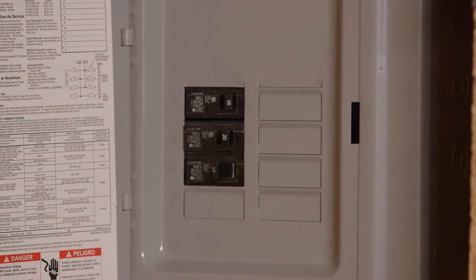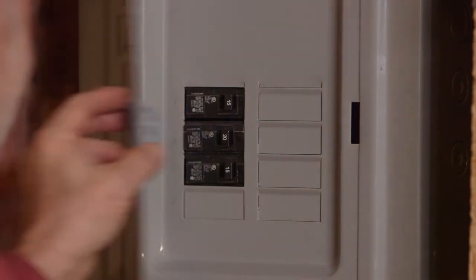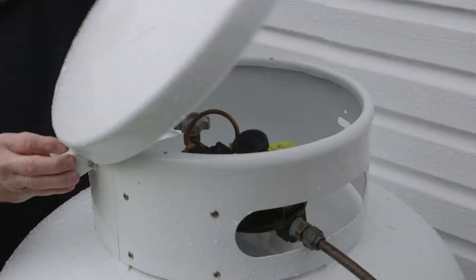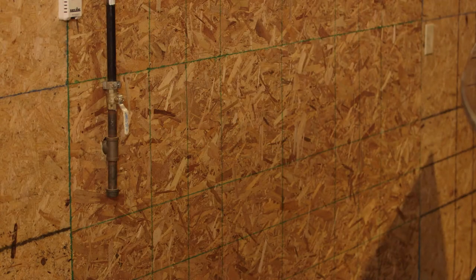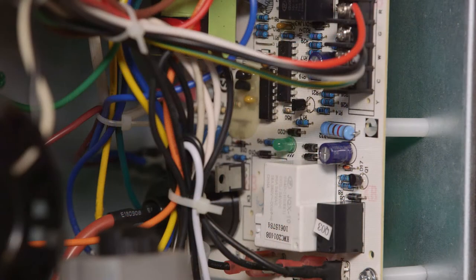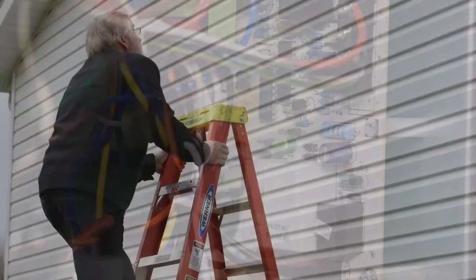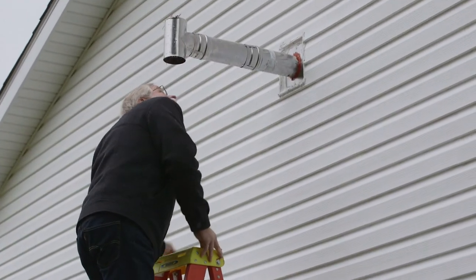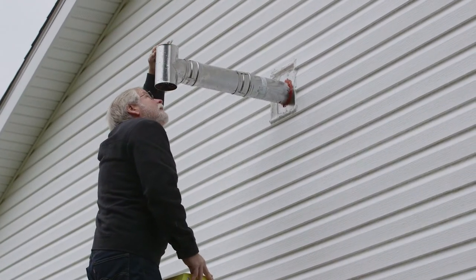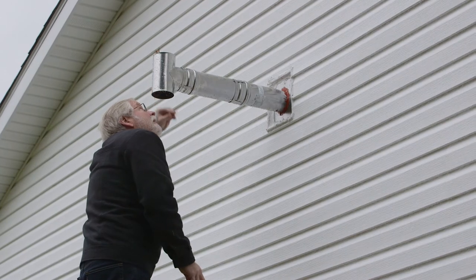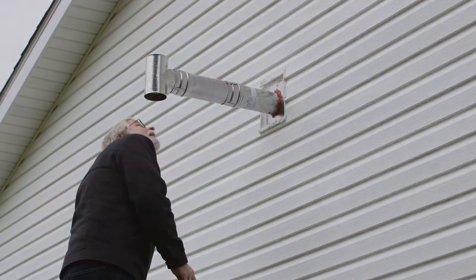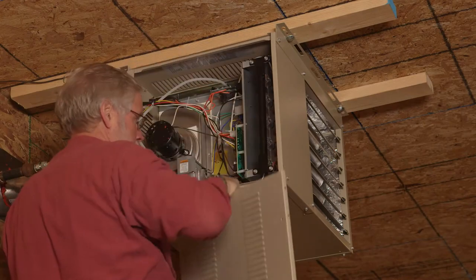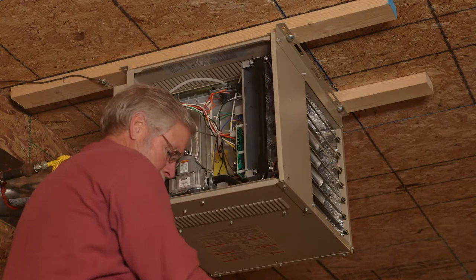Is the main disconnect powered up? Is there a breaker tripped or a fuse blown? Is the gas turned on at the meter and the heater? Is the manual shut off on the gas valve on? Is the unit ignition system in lockout? Two flash code on green LED on the circuit board. Is the pressure switch closed? An obstruction flue will prevent the pressure switch from closing. Check outside vent for blockage, bird or insect nests. Check inside the heater where air tube connects to the exhaust fan for blockage.